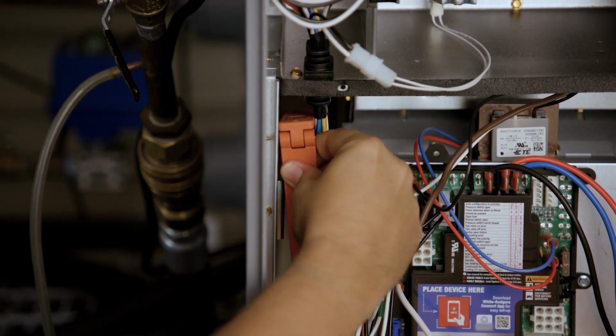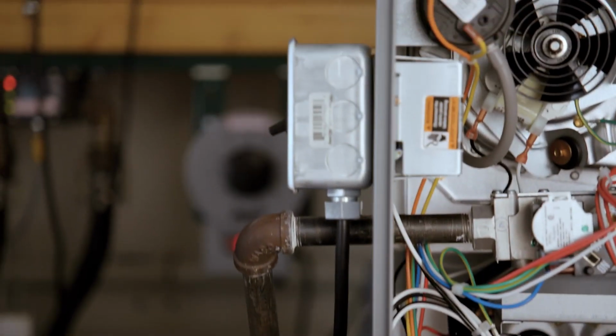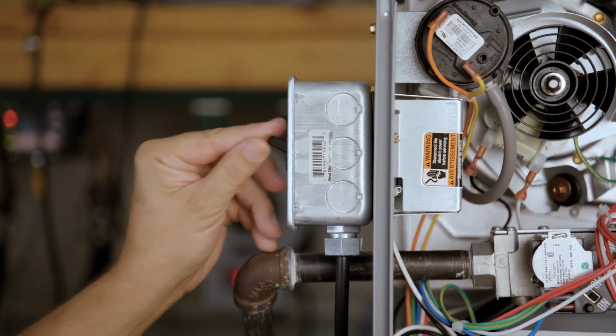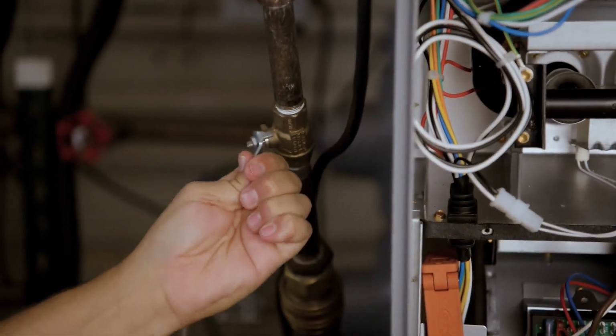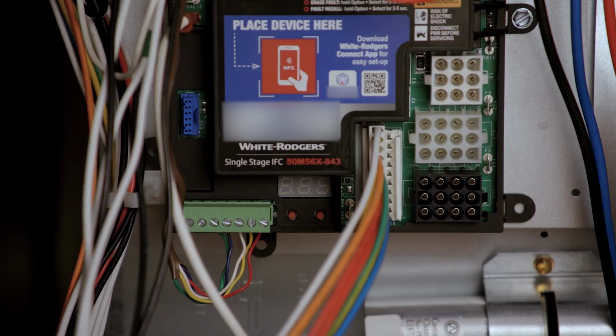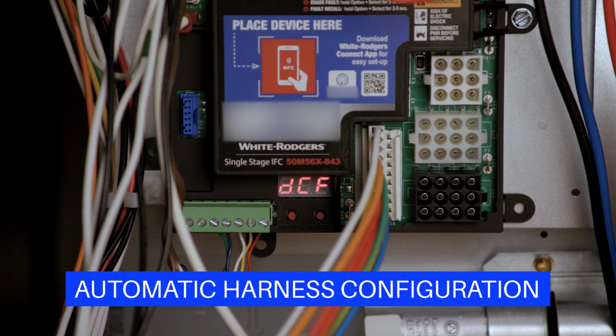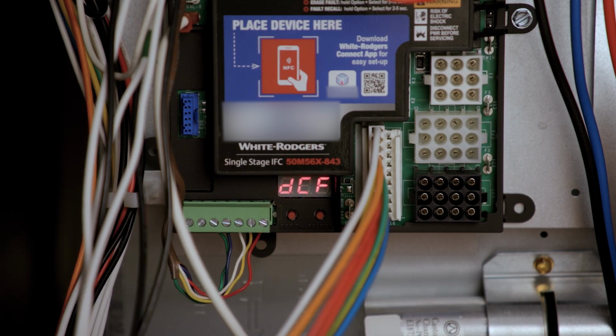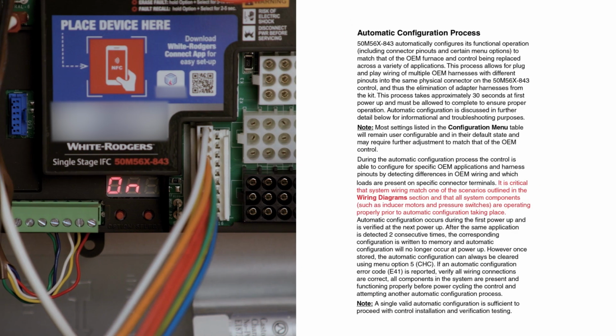The system is now ready to be powered on. Reconnect the electric power and gas to the unit and make sure the door switch is engaged. The 50M56X-843 automatically configures the control to match the harnesses that have been attached. This process takes up to 30 seconds at first power-up. After 2 consecutive matching power-ups, the control will write the configuration in memory. See the installation instructions if the control needs reset for a different application.